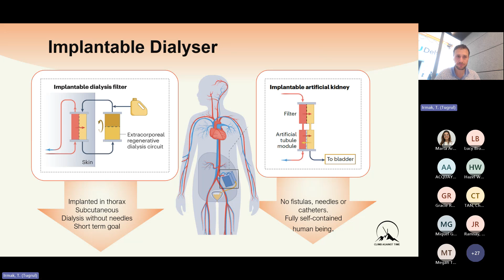So in terms of specifications, such a device would need a thin membrane for free diffusion. We're talking about less than 5 microns. This is on the same order of magnitude as old plate dialyzers, the Kolff dialyzer. Very narrow blood channels. That's where the magic lies. Blood channel resistance should be very small. High surface area. So for diffusive-related processes, this high surface area is needed.